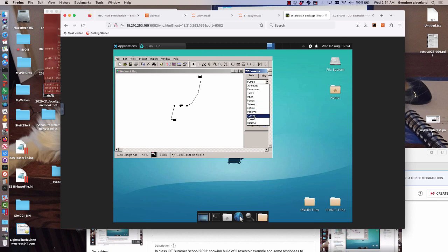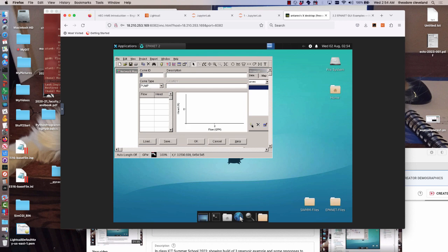Let's add a pump curve. In the browser dialog on the Data tab, I select the keyword curve and click this icon, which is to add a curve. Now it's waiting for input for a pump curve. If you recall, we already determined what the curve would look like. At flow 0, it produces 15 units.